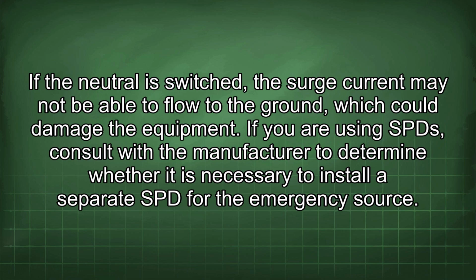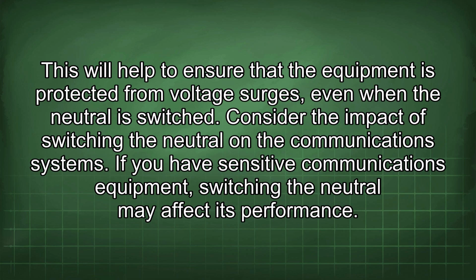the equipment. If you are using SPDs, consult with the manufacturer to determine whether it is necessary to install a separate SPD for the emergency source. This will help to ensure that the equipment is protected from voltage surges even when the neutral is switched.